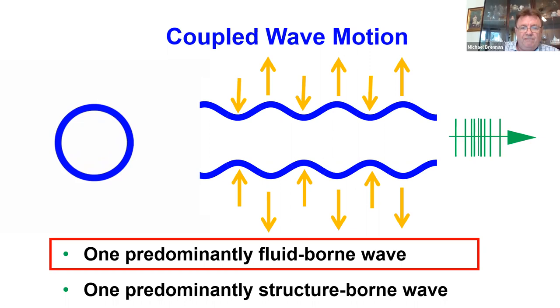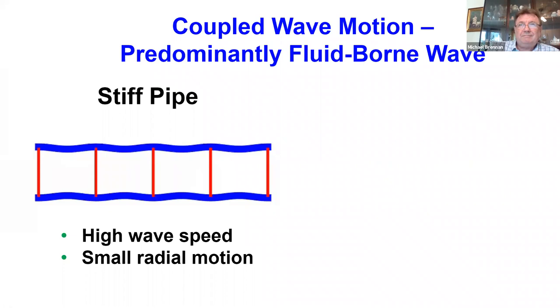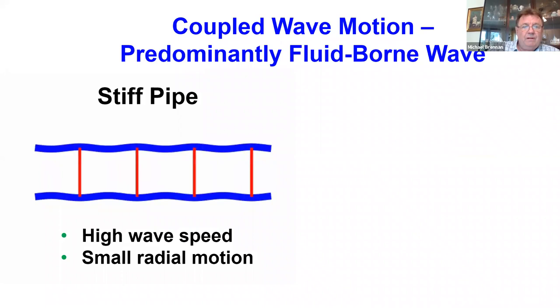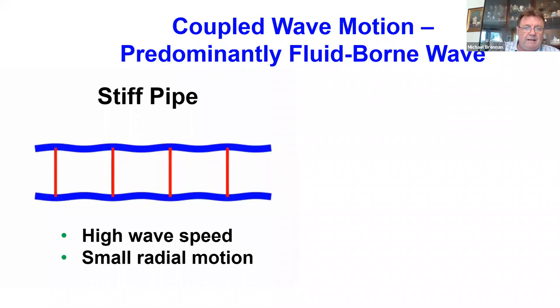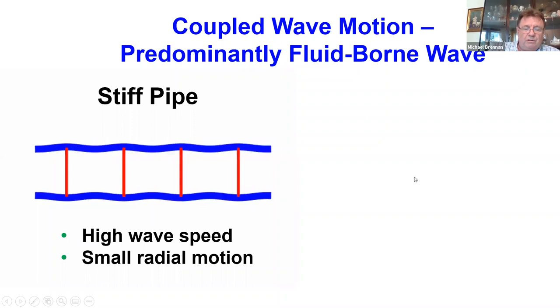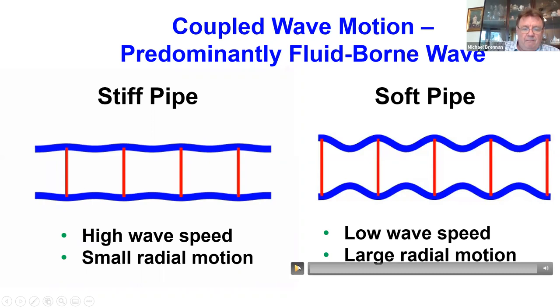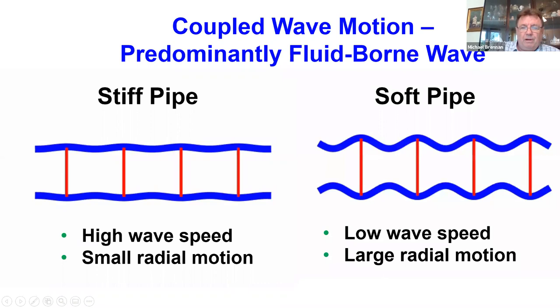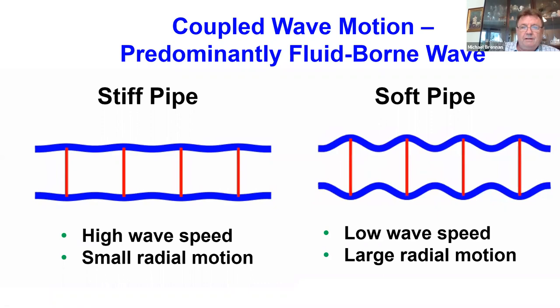The one of particular interest for leak detection is the predominantly fluid-borne wave. If you have a stiff pipe, like a metallic pipe, the coupling is much less, giving a fairly high wave speed and small radial motion. With a soft pipe, the coupling slows the wave down significantly, resulting in a very low wave speed and very large radial motion.